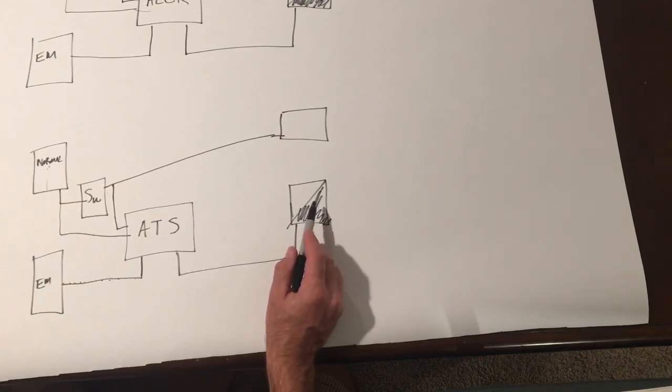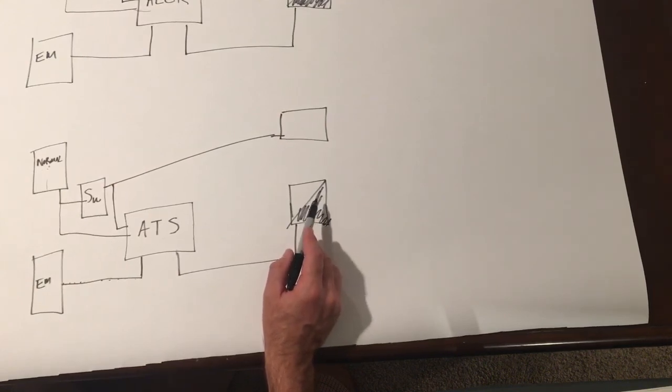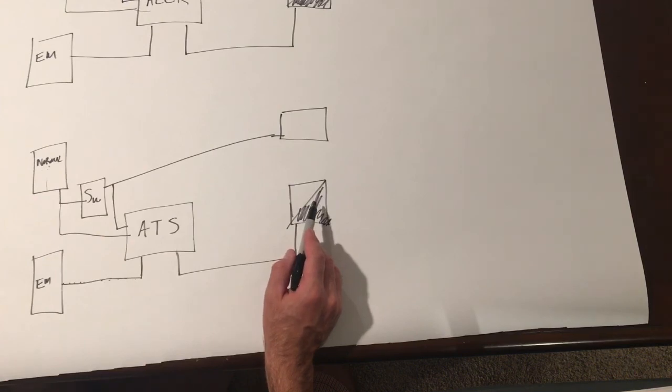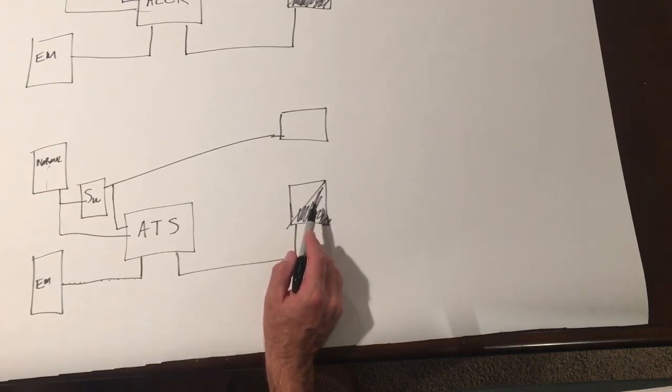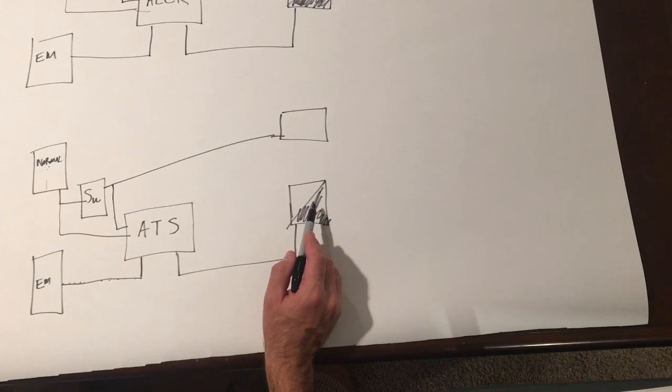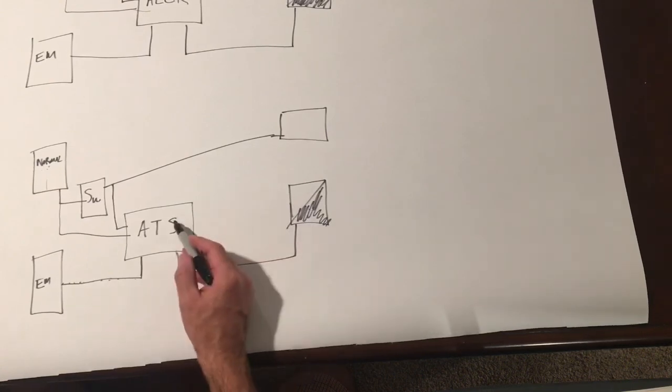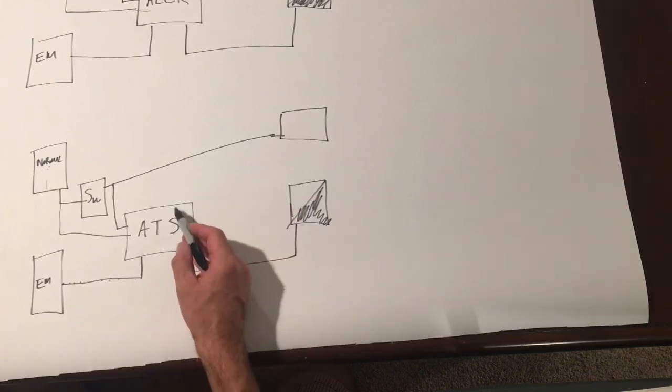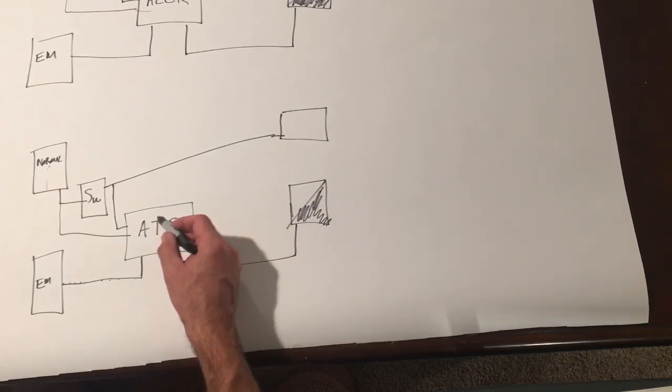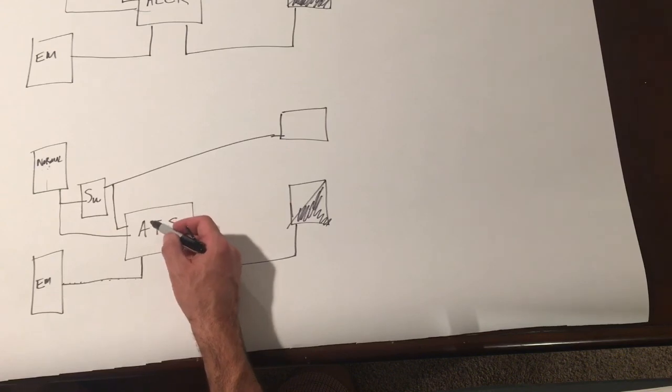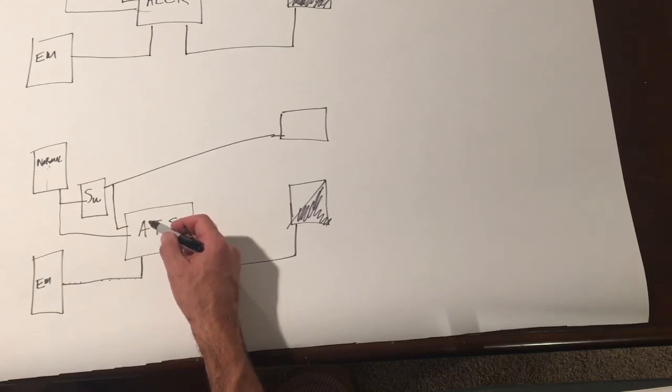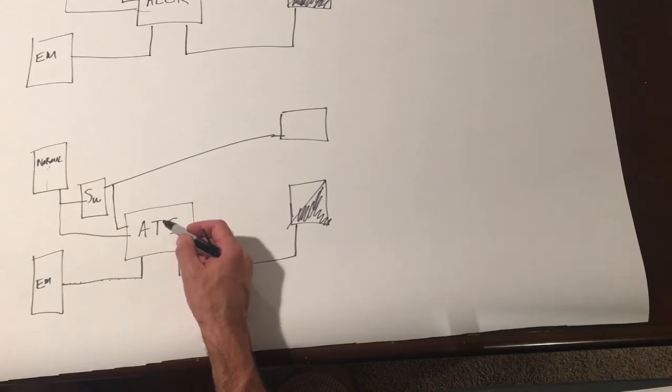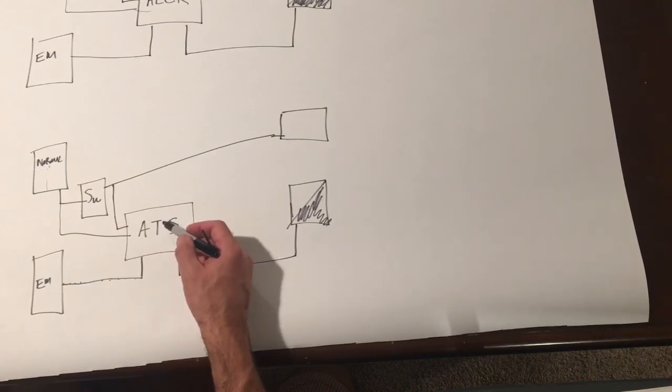One thing I didn't mention was dimming. And if you use zero to 10 volt dimming, that can be used for each of these three applications: shunt relay, automatic load control relay, and automatic transfer switch. They just come with an additional set of contacts, which open up in the event of a power loss and turn the lights on to full bright.